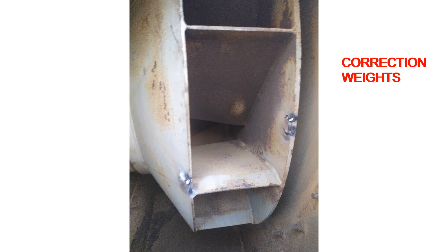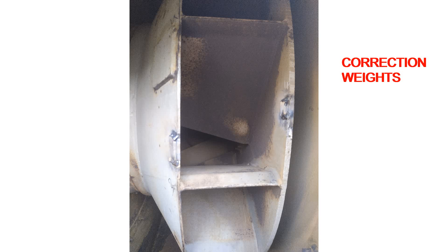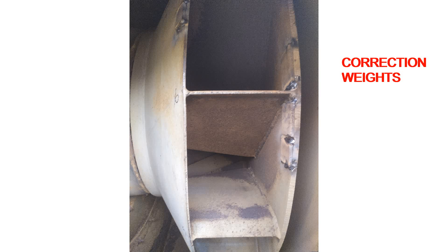I instructed them to replace the corroded nuts and bolts and tighten them to the required torque, and to carry out fan impeller cleaning.